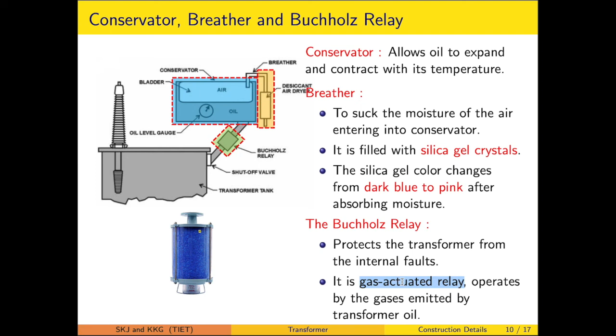So whenever we see that the color is coming out to be pink, the silica gel crystals are replaced. As mentioned, the Buchholz relay is a gas actuated relay. It is able to make a distinction between the normal temperature rise and the gas emitted because of excessive temperature rise arising due to an internal fault. So it is also sometimes suggested that it is used to provide protection against internal faults.